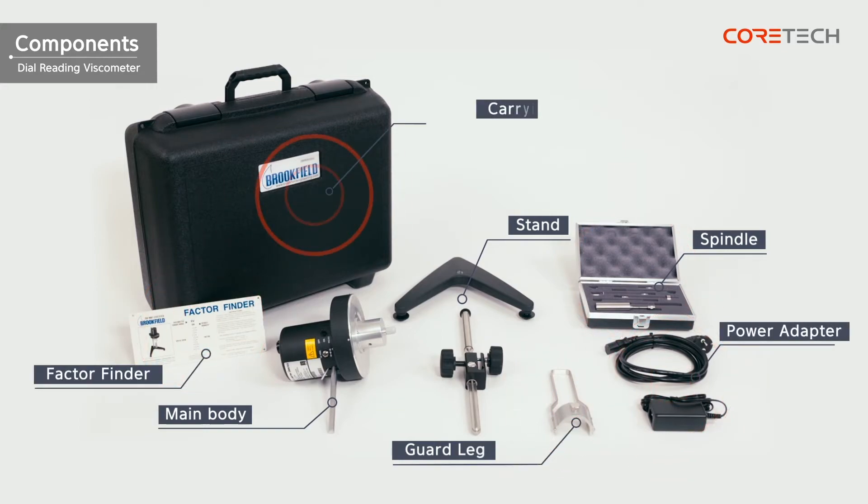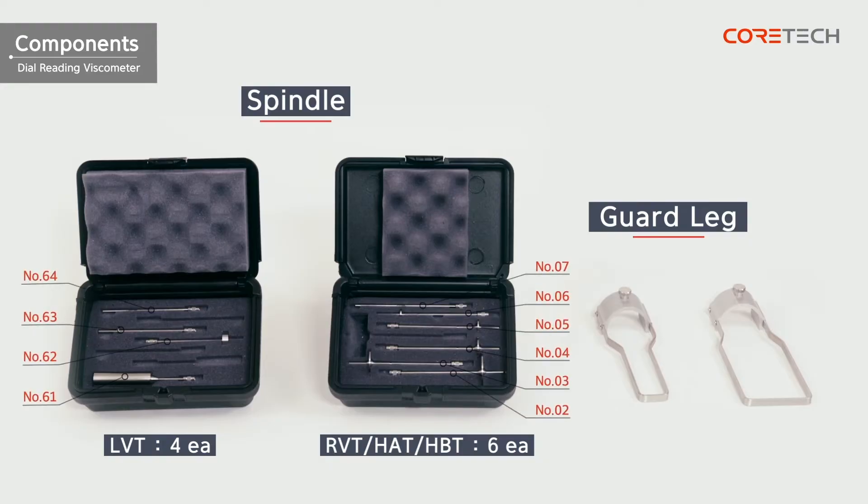The components include the main body, stand, spindle, spindle guard leg, factor finder, power adapter, and carrying case. Models HAT and HBT do not have spindle guard legs. The LVT has four basic spindles, and the other models have six spindles. The guard legs on the LVT and RVT have different shapes and are not compatible with each other.